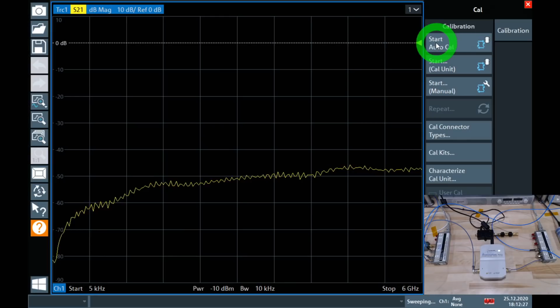Okay, so here we have the screen of the ZNL. At the bottom right, you have a live view of the setup. You can see that the eCal is connected to the two microwave switches. Let's go and perform a very basic auto calibration, which uses the instrument's existing settings to do a calibration. Here we go. Now I click on that. Now right away I get two errors. The first error is that the port 1 is missing.